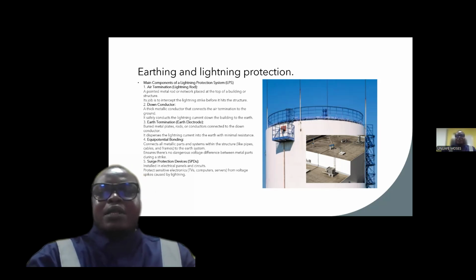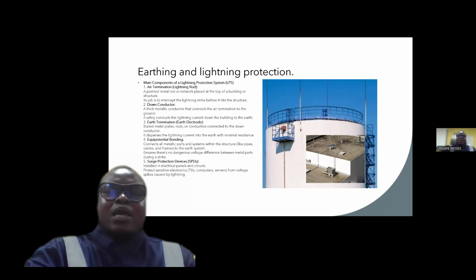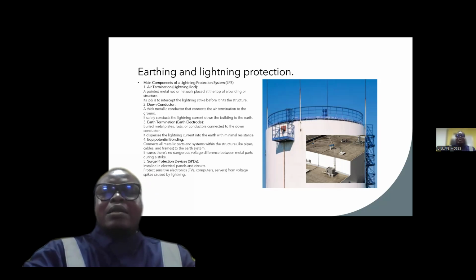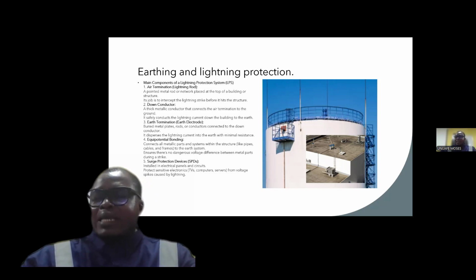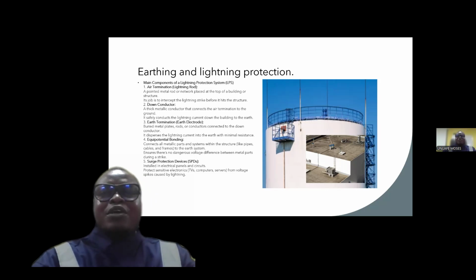Then we also have the lightning counter. Basically, a lightning counter is not actually a protective device, but it helps to mitigate lightning by keeping a proper record. It functions by recording the number of lightning strikes received, and helps to monitor system performance and plan maintenance of your lightning protection. We also have equipotential bonding as part of our LPS. It functions by connecting all metallic parts to prevent different potentials, and is used in hospitals, data centers, and industrial buildings.